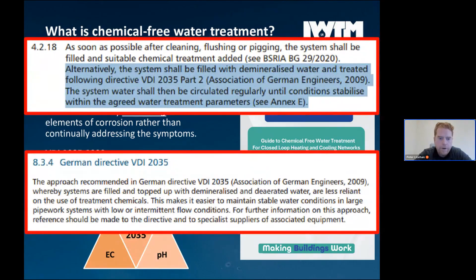So rather than using chemicals, chemical-free water treatment uses equipment that goes in the plant room. It's a 2-product solution, so you need 2 products on your system. You need the reaction tanks on your closed loop system, which use electrochemistry and sacrificial magnesium anodes to consume the dissolved oxygen to below 0.1 milligrams per litre. By consuming dissolved oxygen, it releases magnesium hydroxide, and that is how we regulate the pH to be between 8.2 and 10. So the reaction tank deals with 2 out of the 3 causal elements of corrosion.